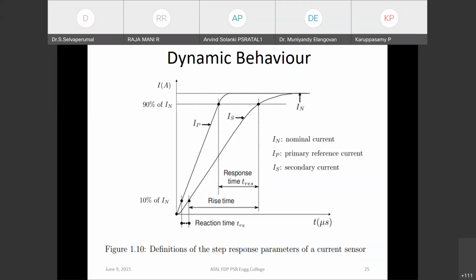The dynamic performance of a Hall effect current sensor is strongly affected by the location of the primary conductor with respect to the air gap in the magnetic core. Increasing the air gap reduces the effect of non-linearity caused by the non-homogeneity of the magnetic core material. But a larger air gap leads to unwanted sensitivity to the position of the measured conductor. Fringing of the field in the air gap reduces the natural shielding of the toroid from unwanted external magnetic field.